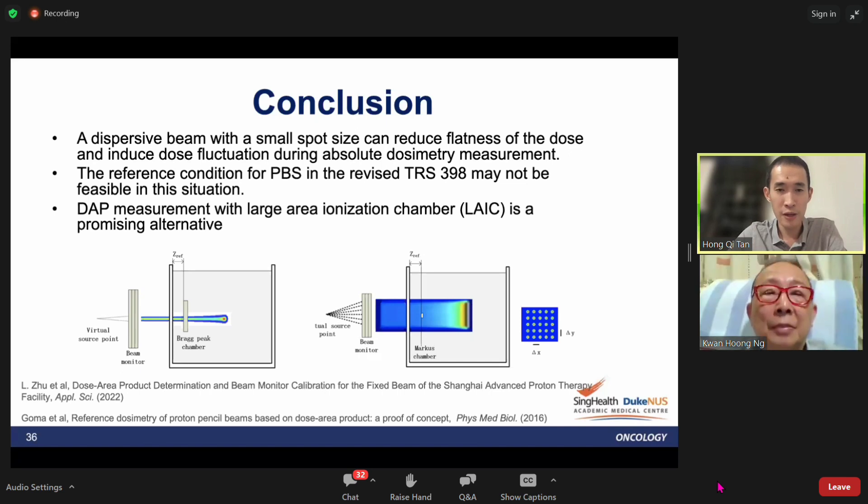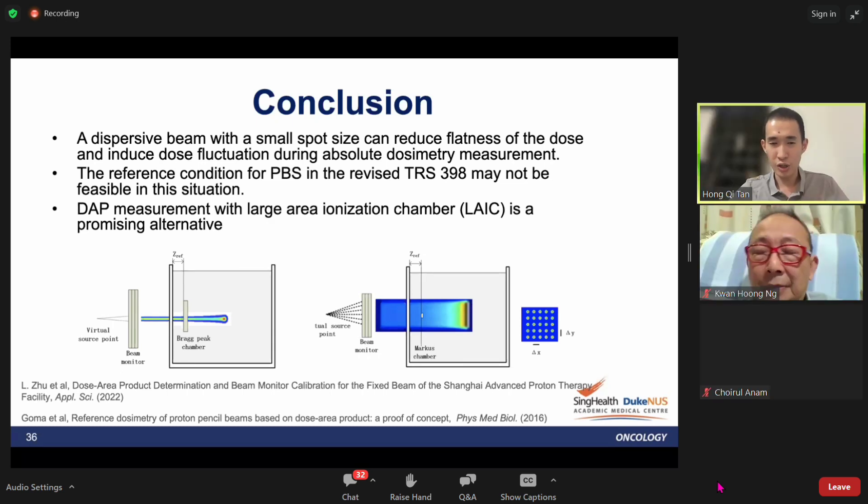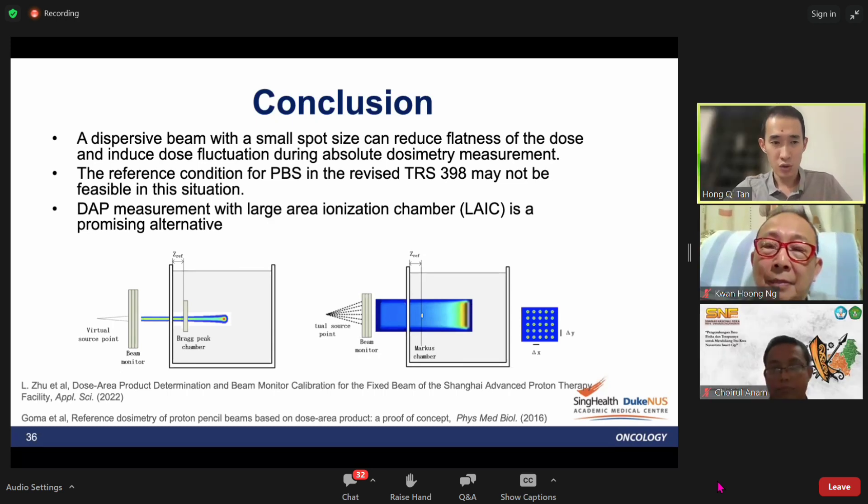The reference condition for PBS in revised TRS-398 may not be feasible in this situation because even with this rectangular spot grid, with these fluctuations you cannot do a very reliable dosimetry. But again, there are still other promising ways forward.